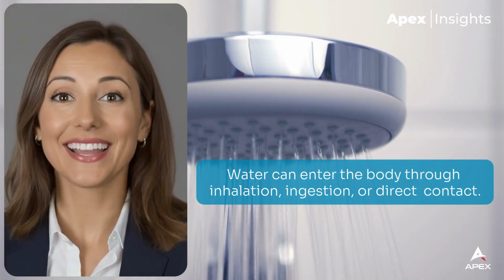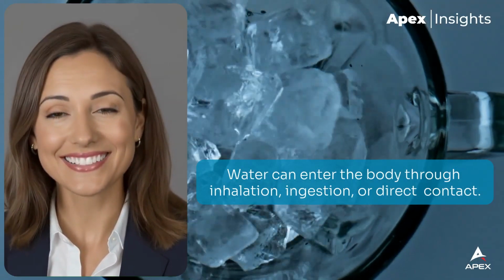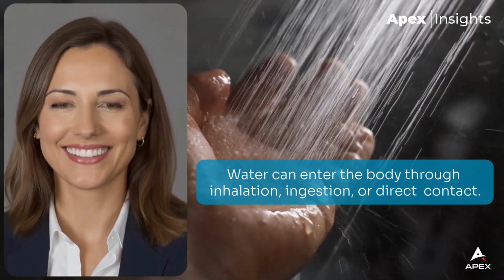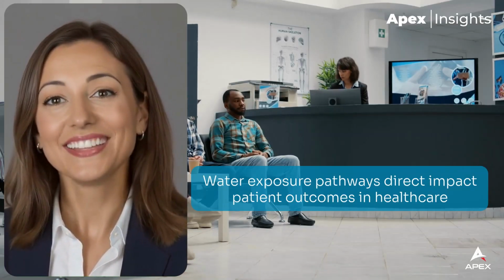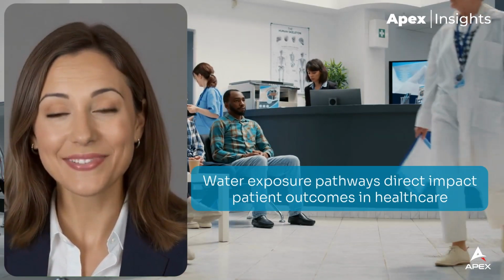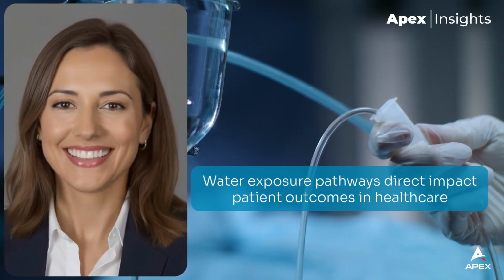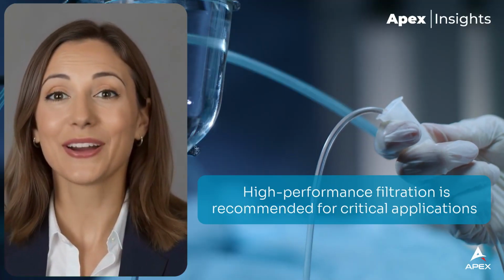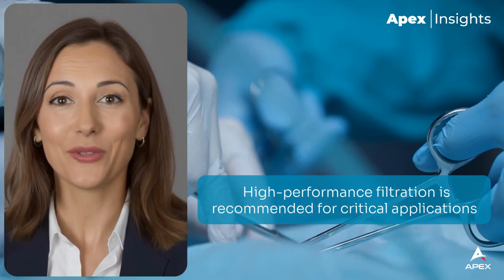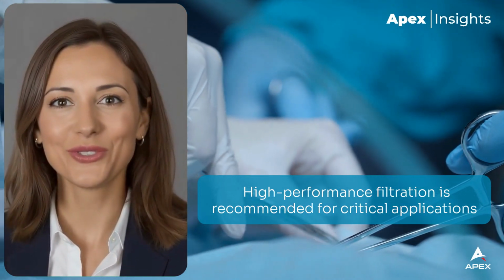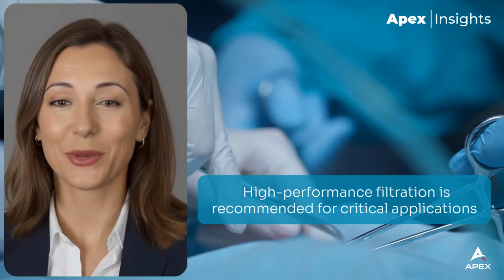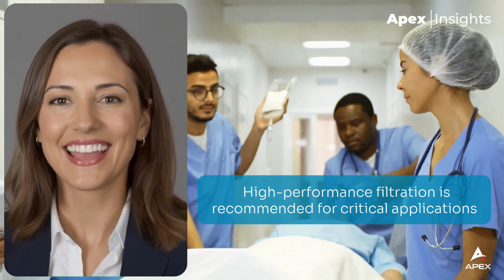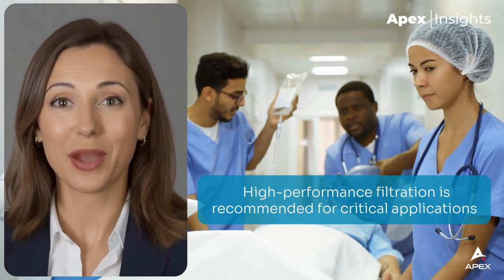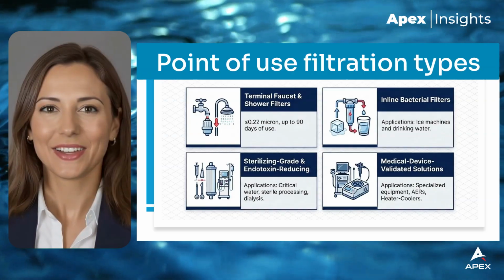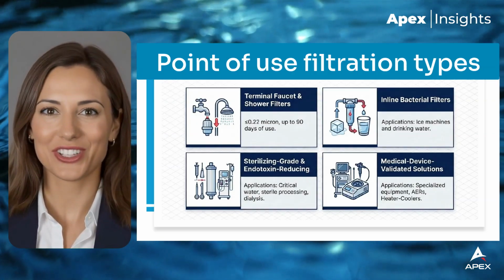So why does this matter? Because water can enter the body in multiple ways, through inhalation, ingestion, or direct contact. And in healthcare environments, those exposure pathways can directly impact patient outcomes. That's why these applications often require high-performance filtration at or below 0.22 microns, sterilizing grade water in critical applications, and endotoxin control where applicable.